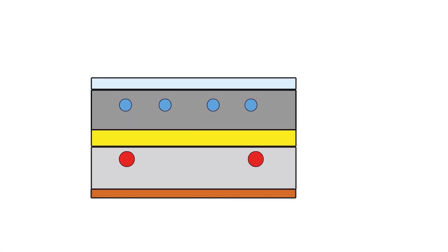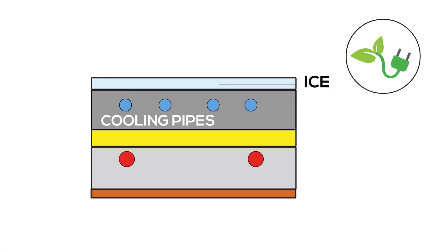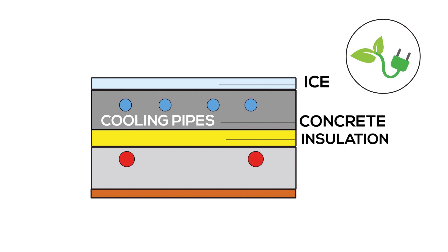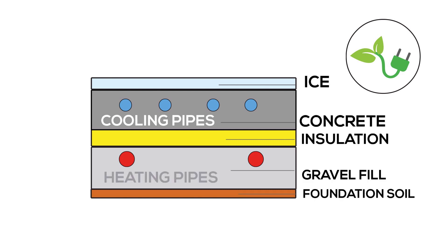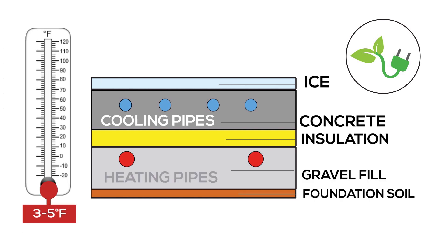Increasing the heat transfer capacity means less energy is required to keep ice made with Real Ice frozen, and therefore, operators will be able to reset their brine temperatures 3 to 5 degrees Fahrenheit warmer.